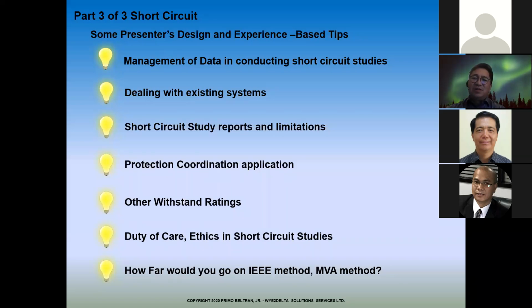The MVA method, for me, is good when you're estimating, but when you're in detailed design, where you'll end up specifying equipment or finalizing protection coordination or arc flash, you use the IEEE method. Now IEC 60909 is also equivalent. What I would say is, if you specify IEC equipment, you have to use the IEC method; if you specify ANSI equipment, then you use the IEEE method. If you use one but specify both standards, then you need to see the difference between the two calculations.